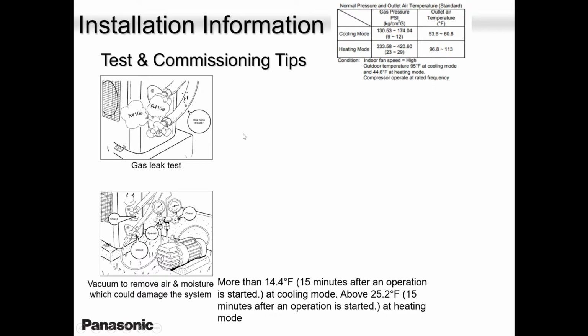Okay, guys. I am in the field most of the time, just like you. So I'm seeing it all the time. Too much nitrogen pressure testing harms this valve. It pushes this valve in. Nitrogen and R410 escape, and when you get rid of the nitrogen to start your vacuuming, you go away with some ounces. Okay, so please watch out for that too.